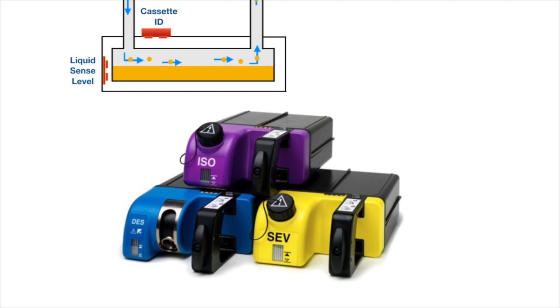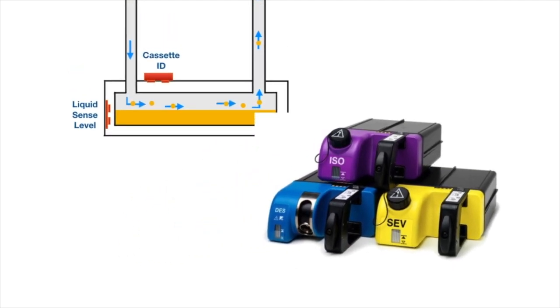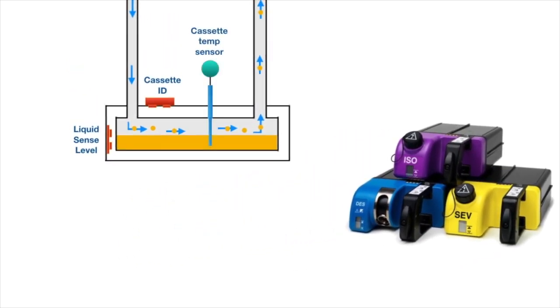Regarding cassette IDs: there are signature magnets that allow the anesthesia machine to identify the agent cassette that is inserted into the machine slot. Temperature in the vaporizing chamber or sump is sensed, and the input is given to the CPU to regulate vapor output.